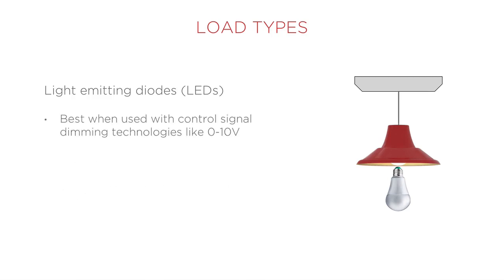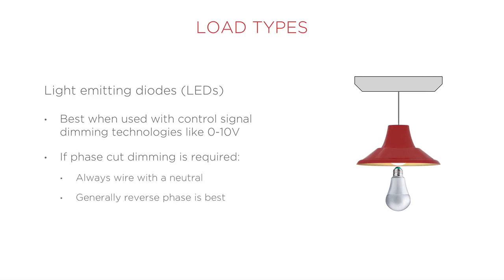When using LEDs, the best practice is to use them with control signal dimming, like 0 to 10 volt dimming. If phase cut dimming is required, always wire an LED fixture with a neutral, and generally, reverse phase is better, therefore use with the adaptive phase dimmers.